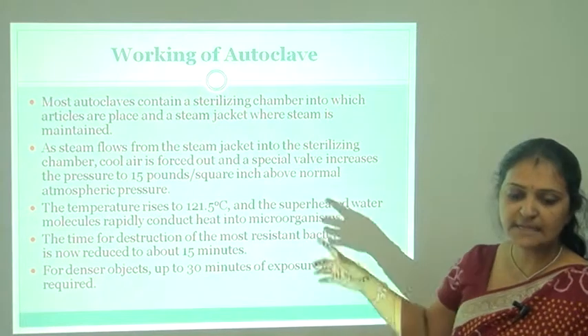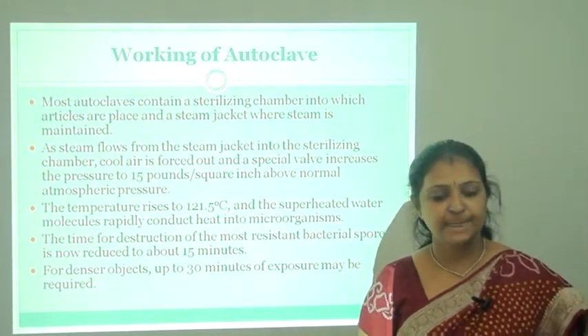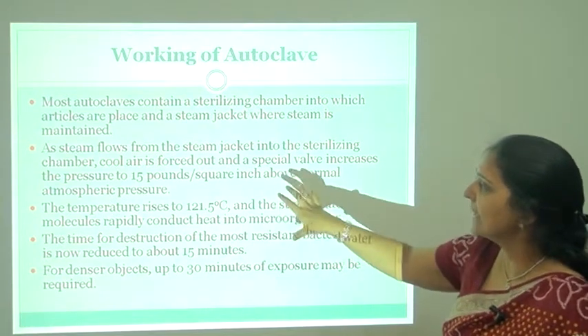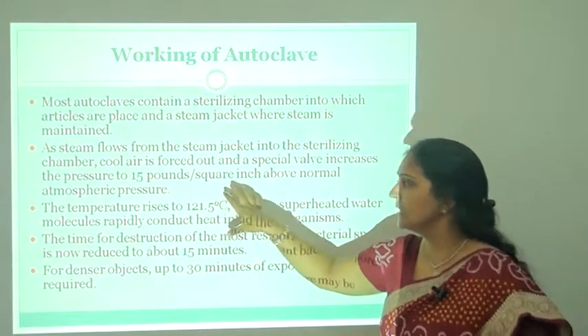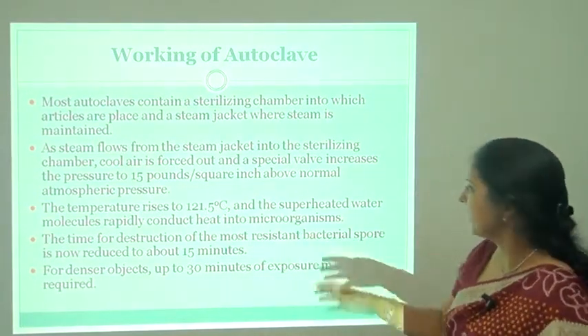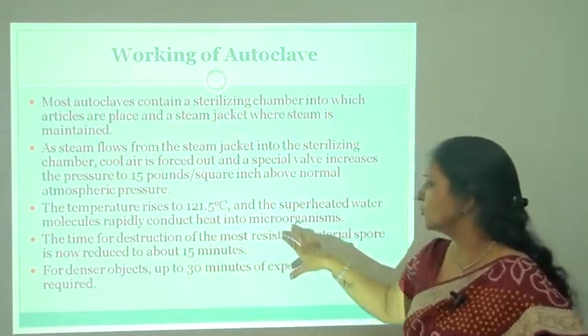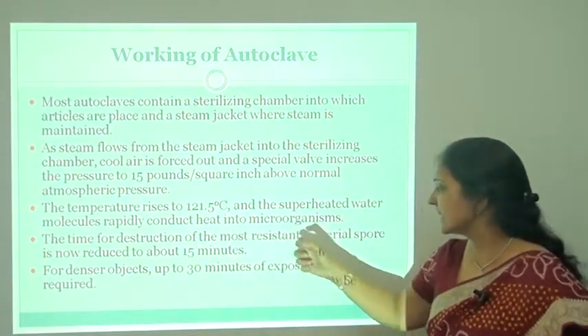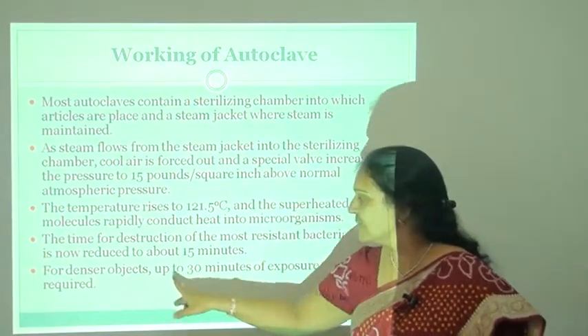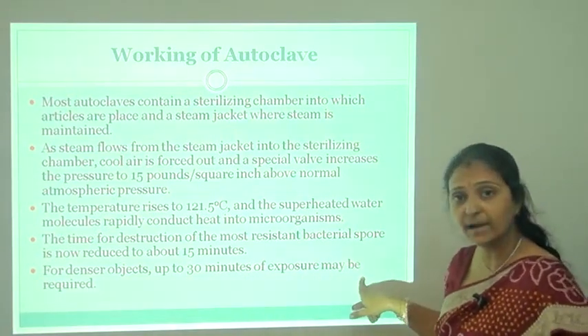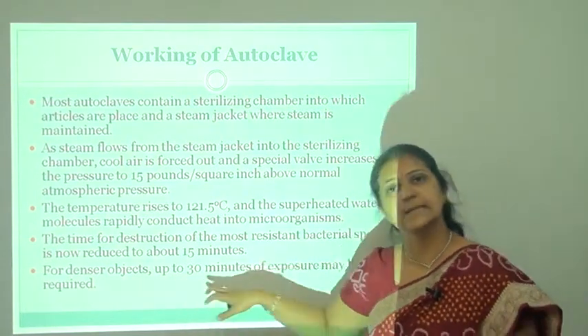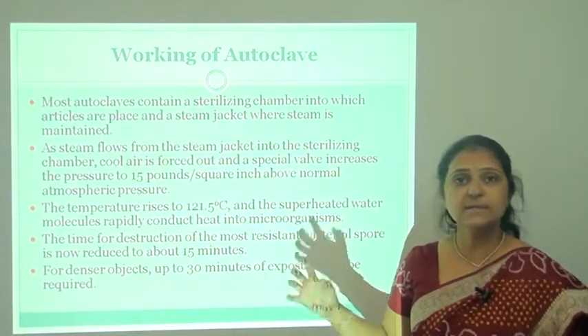Most autoclaves contain a sterilizing chamber in which articles are placed and a steam jacket where steam is maintained. As steam flows from the steam jacket into the sterilizing chamber, cool air is forced out and a special valve increases the pressure to 15 pounds per square inch above normal atmospheric pressure. The temperature rises to 121°C and the time for destruction of the most resistant bacterial spore is reduced to about 15 minutes. For denser objects, up to 30 minutes of exposure may be required because steam takes much longer to penetrate denser objects.